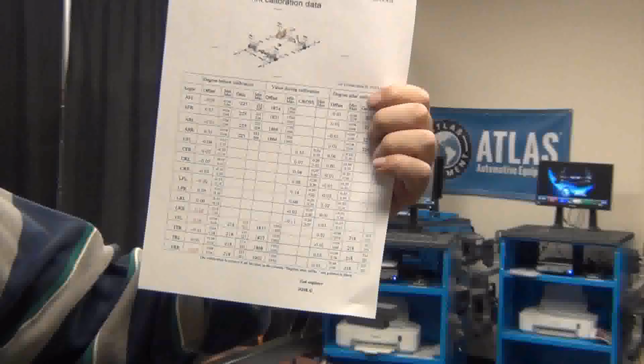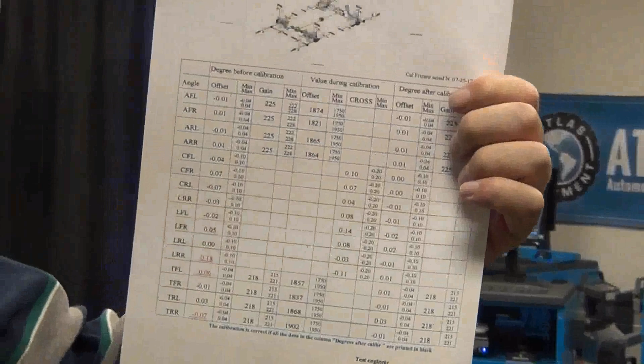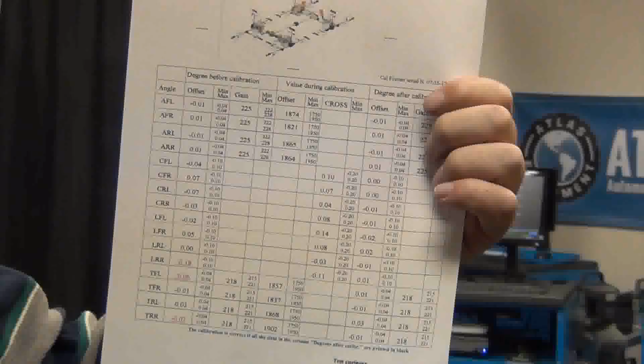Right, so this here is what the calibration report looks like. It will show you your before and your after readings. It'll show you what adjustments have been carried out. It will show you the date and the time, the verified date and time. And your machine is now calibrated.